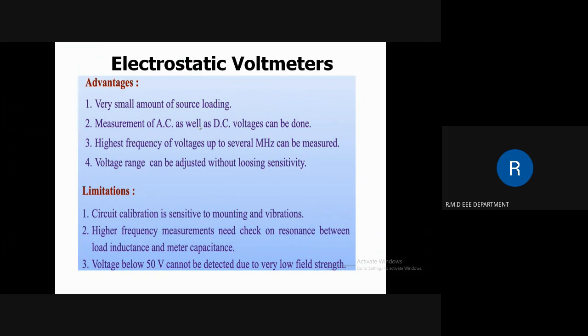Coming to the limitations of this electrostatic voltmeter, the calibration is sensitive to mounting and vibration. For higher frequency measurements, checks have to be done on resonance between the load inductance and the meter capacitance. And voltages below 50 volts cannot be detected due to very low field strength.